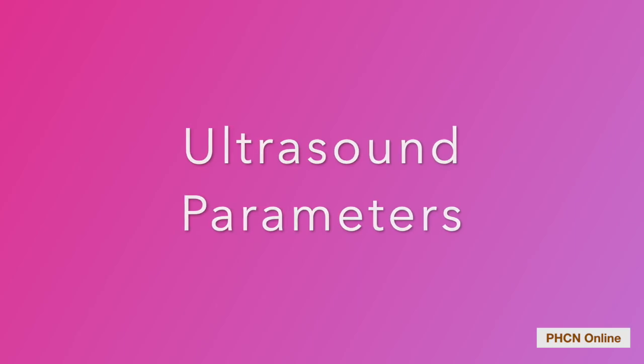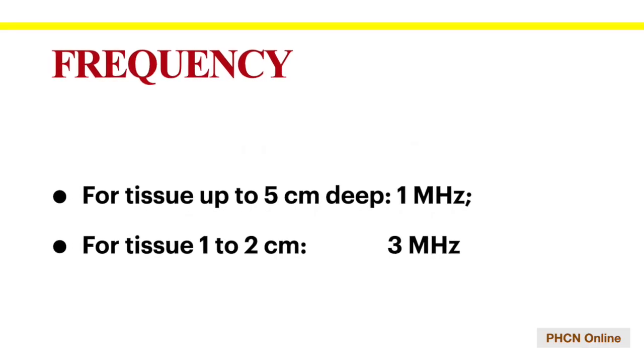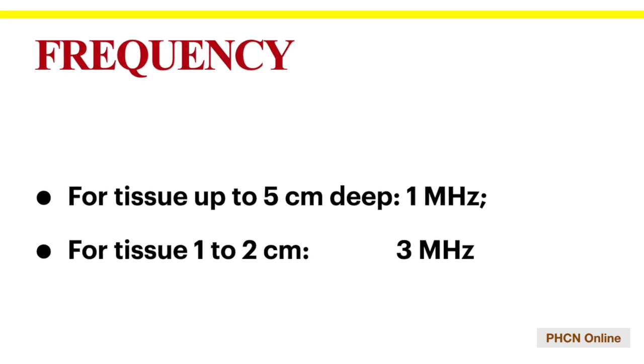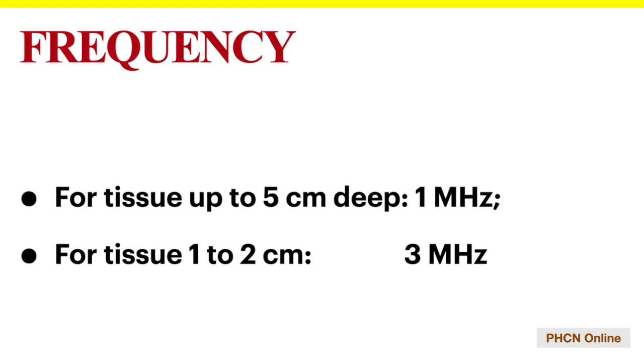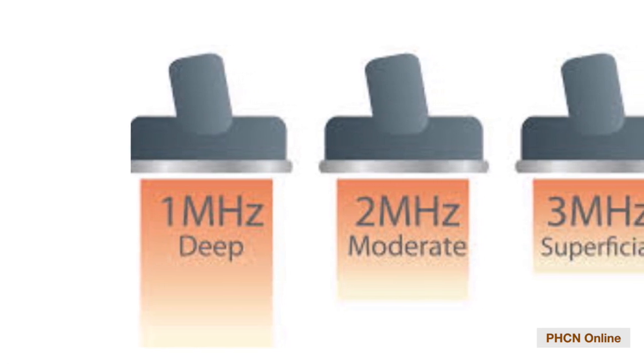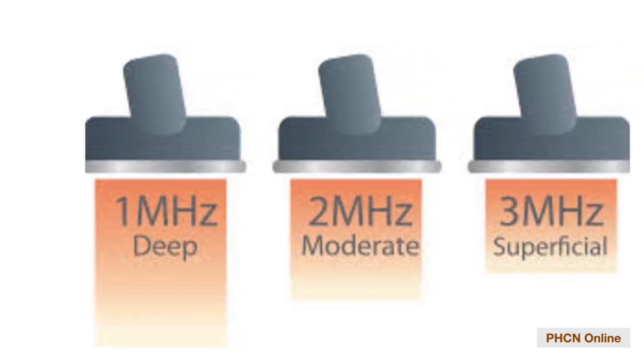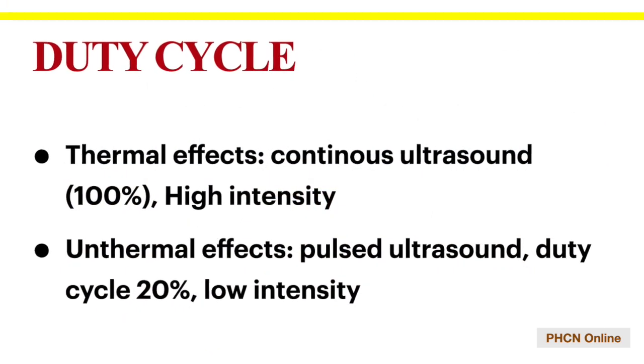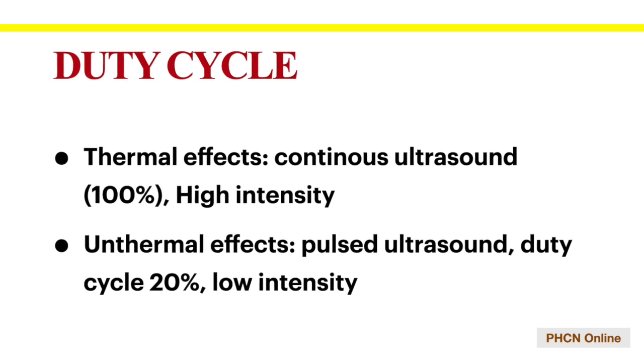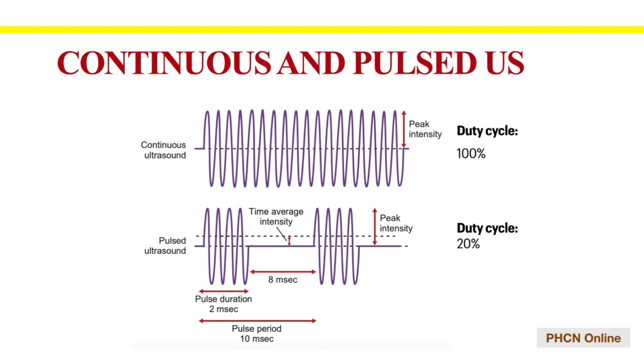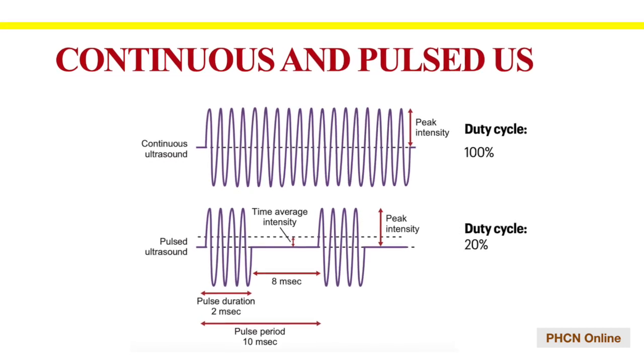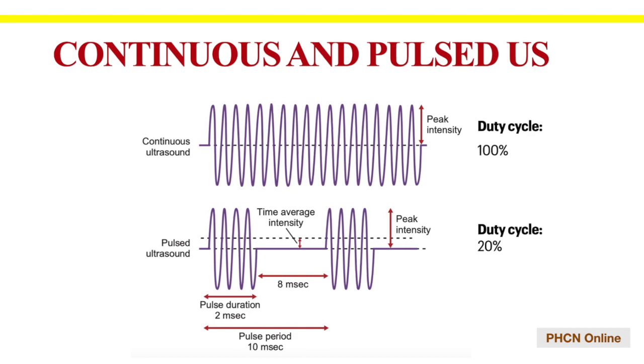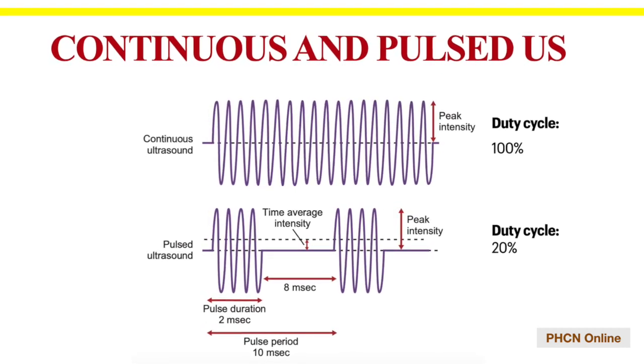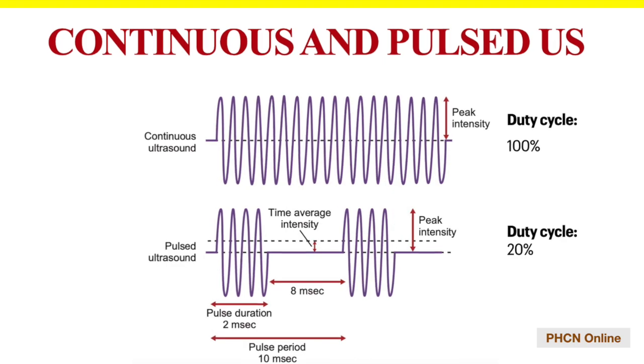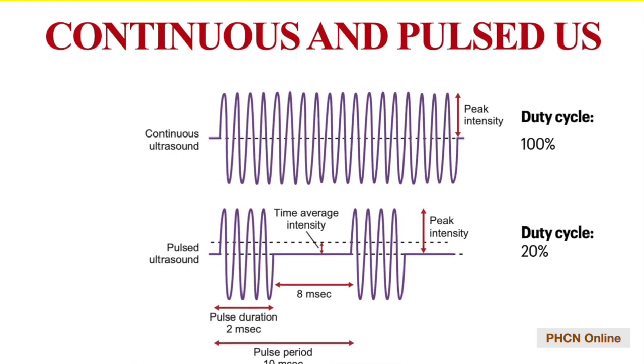Ultrasound treatment parameters. Frequency. The frequency is selected according to the depth of the treated tissue. For tissue up to 5 cm deep, 1 MHz is used, and 3 MHz is used for tissue 1 to 2 cm deep. Duty cycle. The duty cycles are selected according to the treatment goals. When the goal is to increase tissue temperature, a 100% continuous pulse cycle should be used. When ultrasound is applied for non-thermal purposes, a duty cycle of 20% or less is recommended.